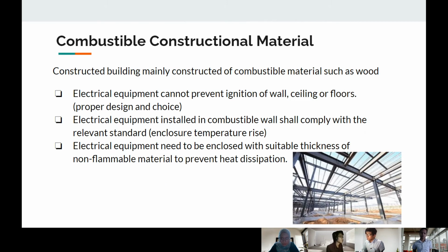Next is combustible construction material. The construction material in the image below is steel, and the combustible material is wood. Electrical equipment cannot prevent ignition of walls, ceilings, or floors. This can be prevented by proper design and choice of material. Electrical equipment installed in a combustible wall shall comply with the relevant standard, to prevent enclosure temperature rise. Next, electrical equipment needs to be enclosed with a suitable thickness of non-flammable material to prevent heat dissipation.